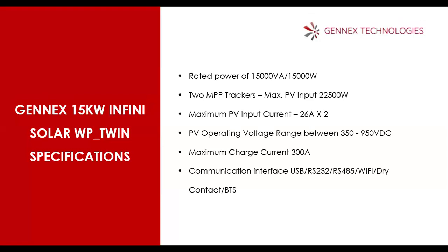So for instance, if you have a solar panel of about 45 volts or, let's say, 50 volts, you can connect up to 18 or 16 in series. And if that same panel has an Isc of about 13 amps, you can put that 18 into a 2-string and connect it on one PV input. You can do the same on the other PV input, and you can configure it to have more solar panels, but the maximum you'll be generating is about 22 kilowatts.